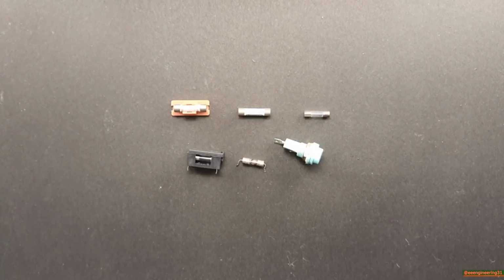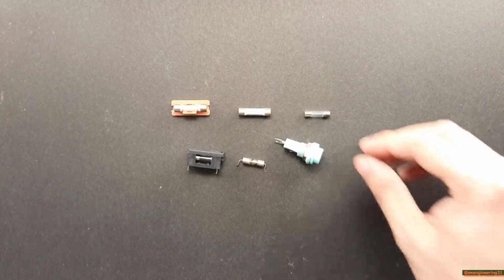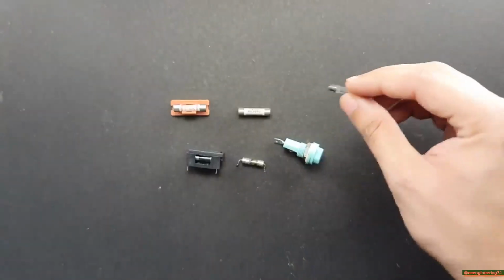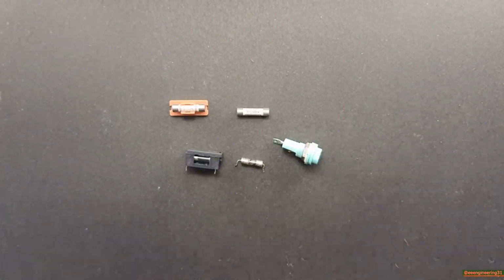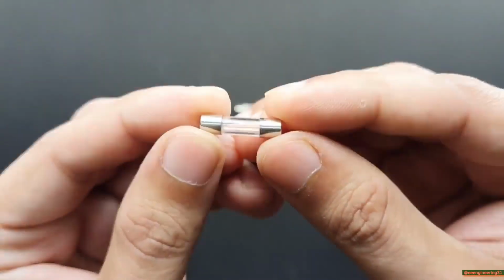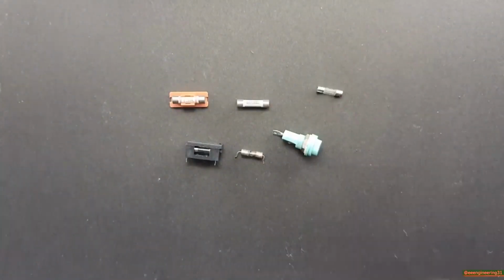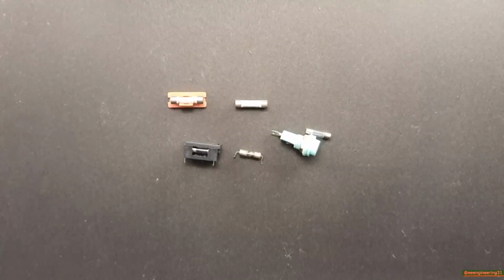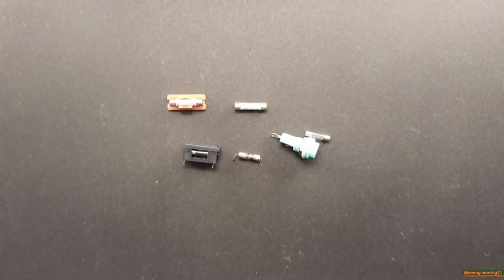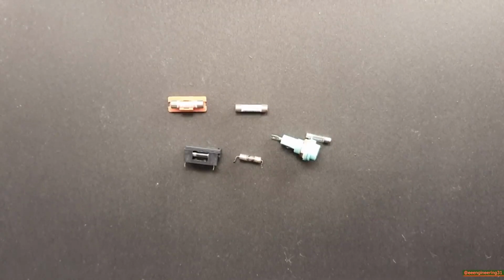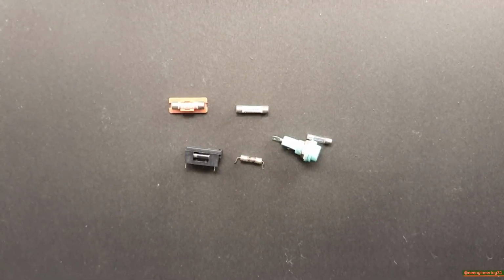Now let's look at the common failure reasons of a fuse. A short circuit pulls too much current through the fuse, so it blows. Sometimes you may run across a fuse which has fatigued with age and use, finally failing. If it is a glass fuse like this, take a look at the insides. When the two wires are almost touching and there is no discoloration, the fuse blew gently, and there is a possibility that the circuitry isn't shorted. The fuse wire just gets warm enough to fracture, but there is no malfunction in the circuitry.